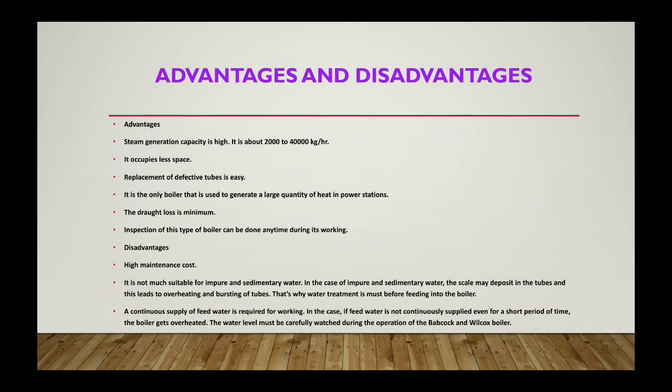So there must be a mud collector present. That means if you supply water which has some impurities and sedimentary objects or debris, then when it is supplied to the water tubes for producing the steam, it may be overheated. Actually these particles absorb very much heat, so the tube may burst.